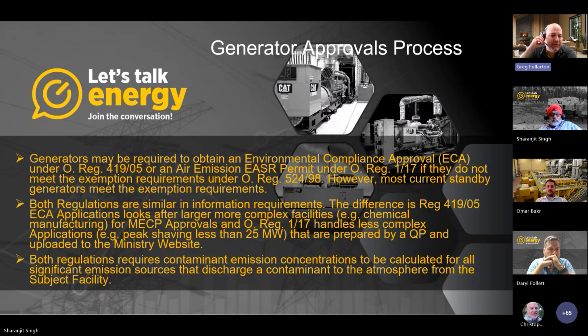Generators may be required to obtain an Environmental Compliance Approval under O. Reg 419/05, or an Air Emission EASR Permit under O. Reg 117, if they do not meet the exemption requirements we discussed. That's under O. Reg 524/98. However, most current standby generators meet the exemption requirements.